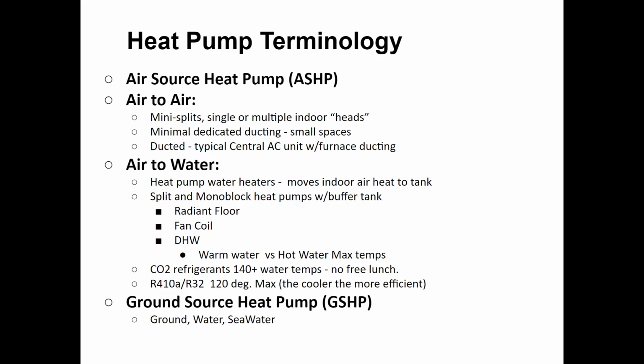In the case of a ground source heat pump, rather than grabbing the heat from the air, or in the case of cooling, rejecting the heat to the air, you actually use the ground itself, or water within the ground, or a pond nearby. You'll still call it a ground source heat pump if it's a pond, as the place where the heat is drawn from and where it is rejected to.